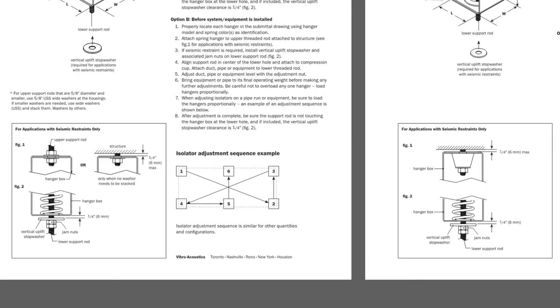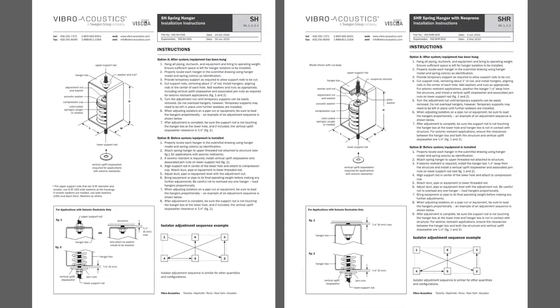Here we can compare the SH with the SH-R instructions side by side so you can see an important difference. The top of SH isolator hanger boxes can be secured while the top of SH-R boxes need to be free from direct contact with structure. The upper isolator portion must be free to move. It is unfortunately too common to see SH-R isolators secured tight to structure which short circuits the rubber element isolation portion of the isolator.